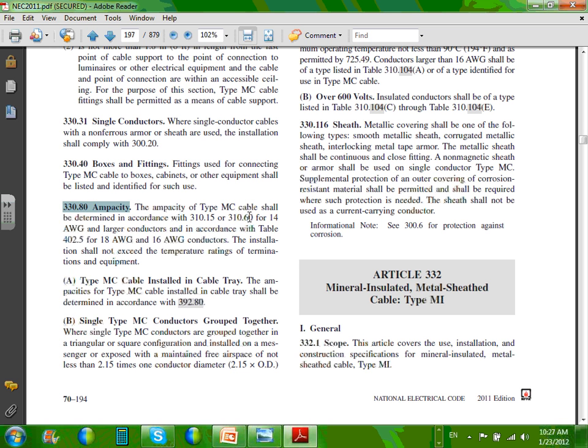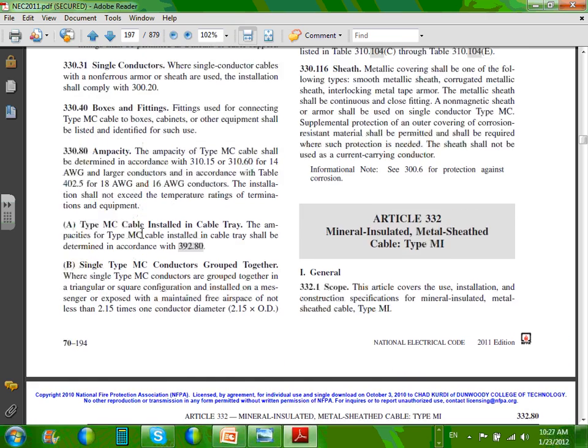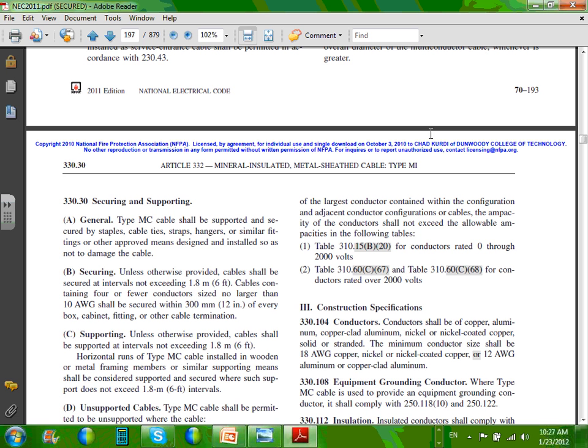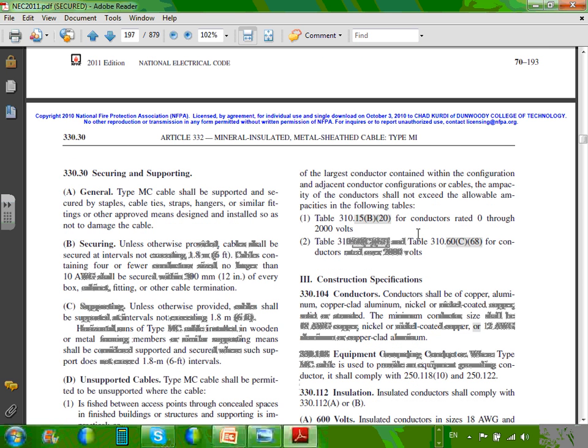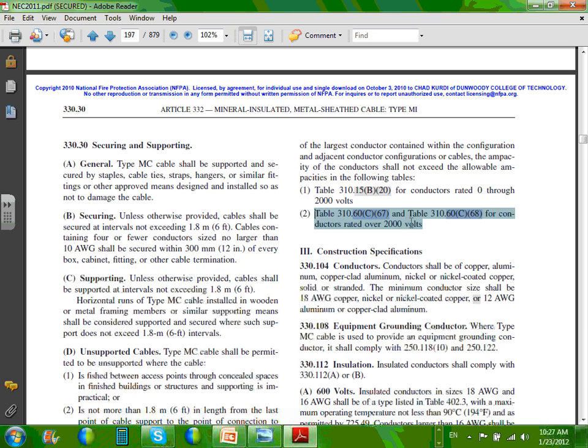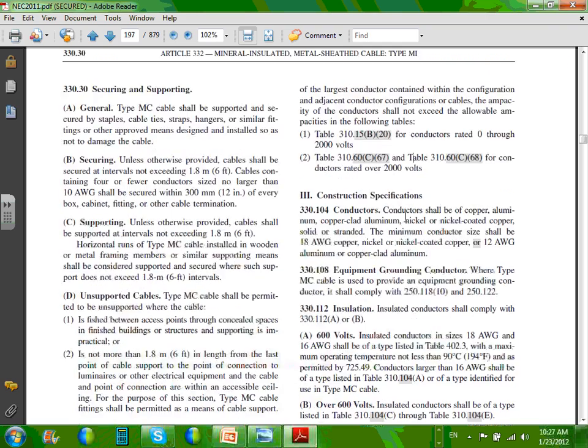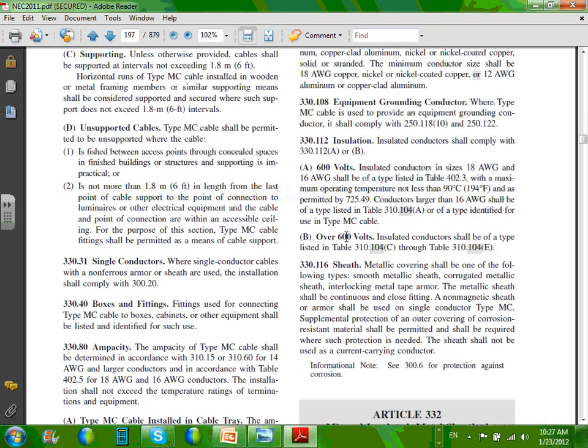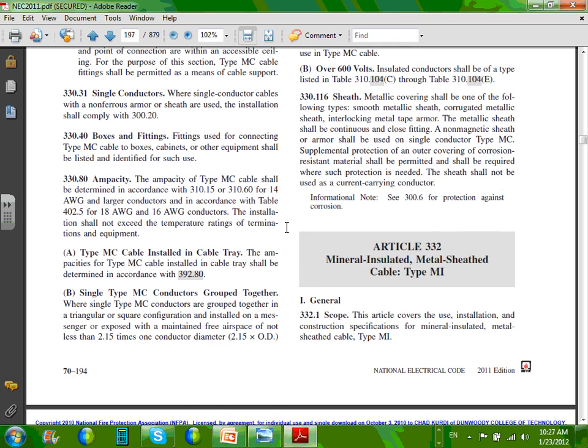.80 says ampacity for the conductors is going to be based on 310.15, and you can use up to... ampacity shall be determined from this table, 14 and larger from this table for cables. And if it's more than number 1, you're going to be sizing it from 310.15(B)(16) under the 60-degree column. There's also higher than 600 volt, guys. You also go to different tables if it's higher than 600 volt. Construction over 600 volt and sheath and so forth. So it's not a whole lot to it.